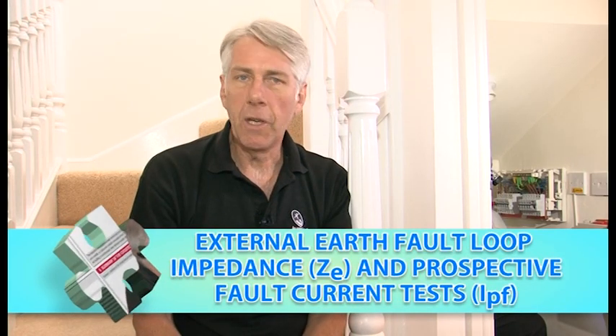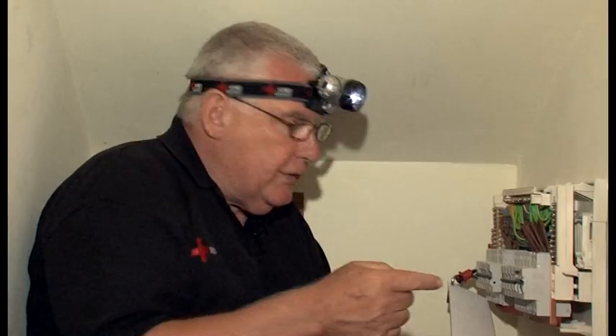Okay, we've finished the visual inspection of a sample of electrical equipment around the property. We've also undertaken R2 tests and R1 plus R2 tests where appropriate, and we've kept our sketch updated, including any observation codes, R2 readings and the R1 plus R2 readings of lighting circuits. So what now, Tony? What I would like to do now is undertake an electrical test to verify that this property does actually have an earth, rather than just assuming so because we've seen a cable. But first, I want to check the polarity on the incoming supply.